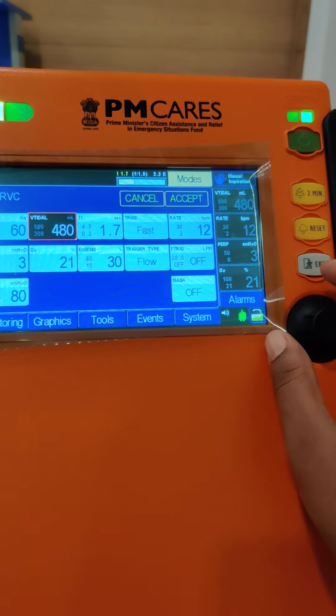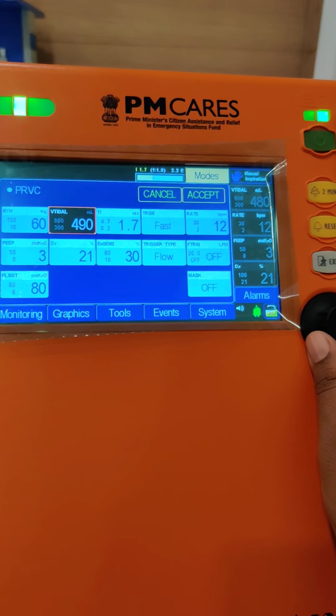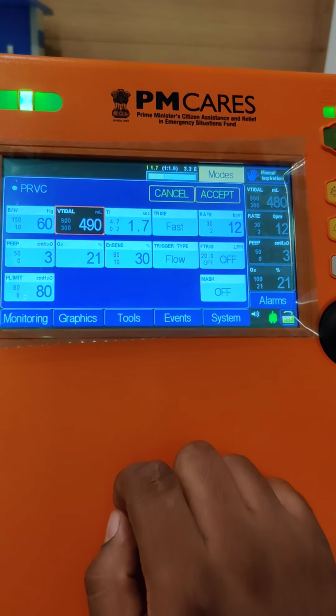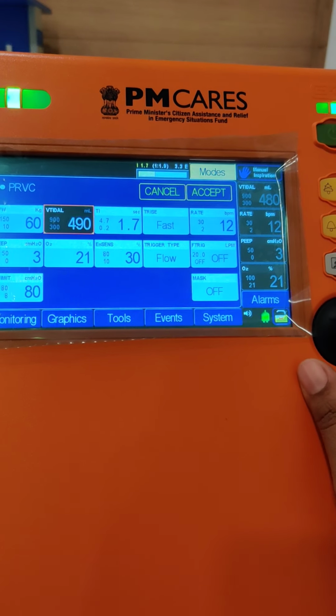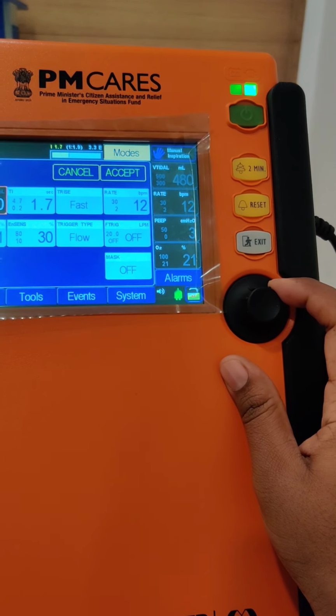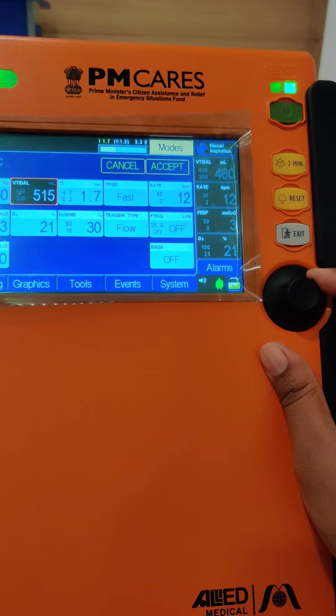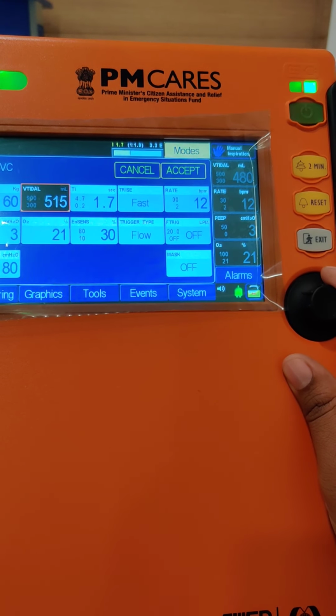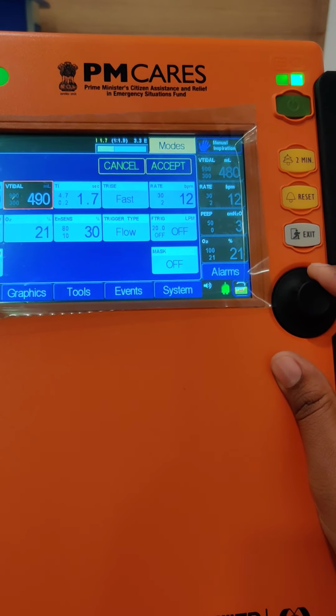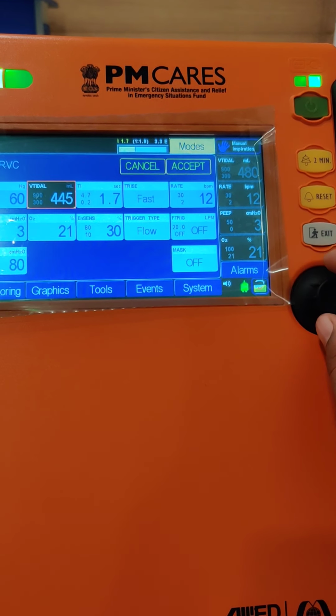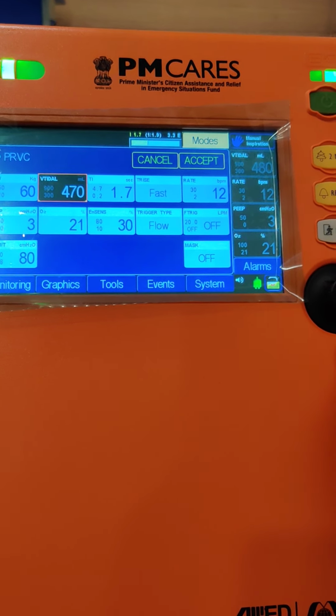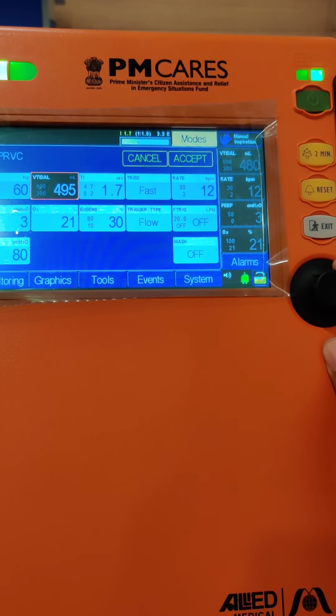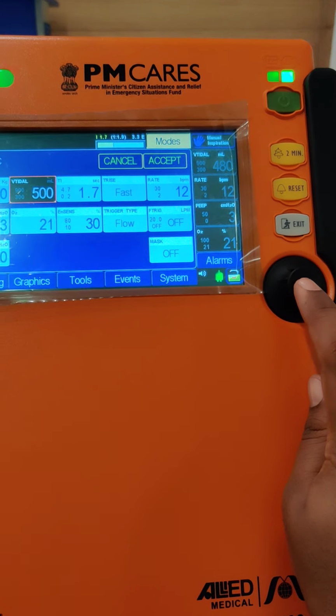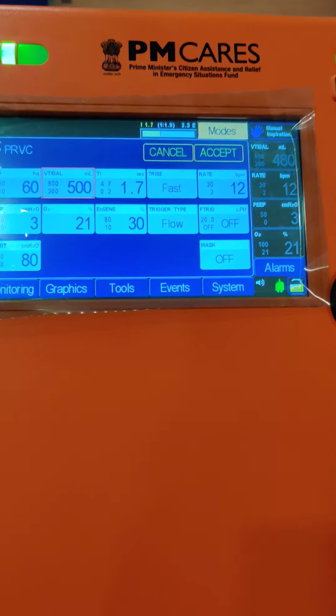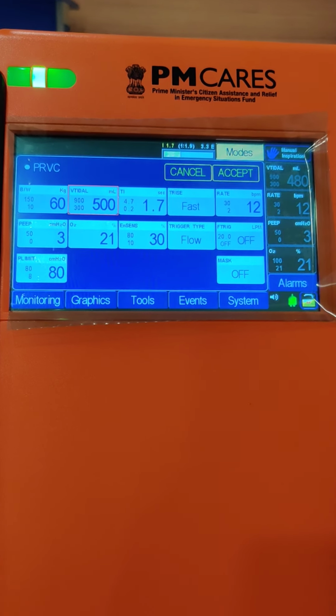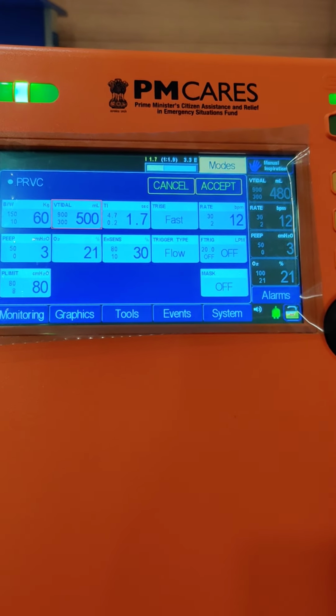So if I want to deliver 500 ml of tidal volume, I'll select this tidal volume parameter over here, and for increasing it to 500 I'll use this knob. If I rotate this knob clockwise, the values will increase, and if I move it anti-clockwise, the values will decrease. For confirming 500 ml, I'll press this knob again. So the set tidal volume right now is 500 ml.